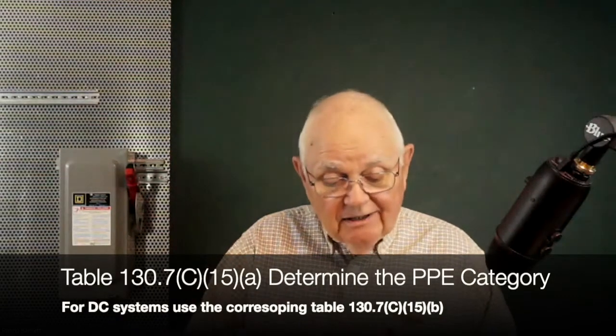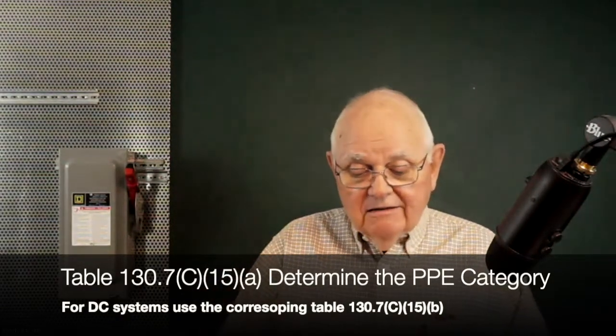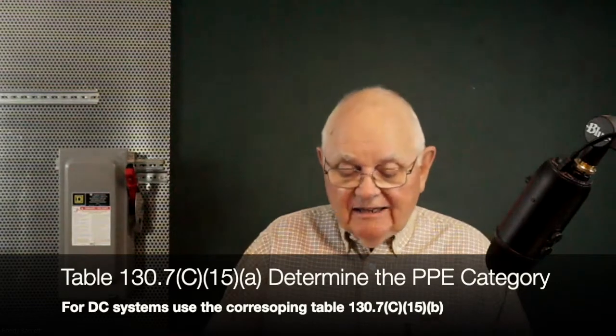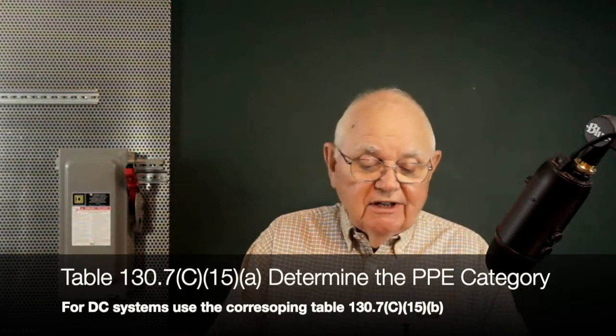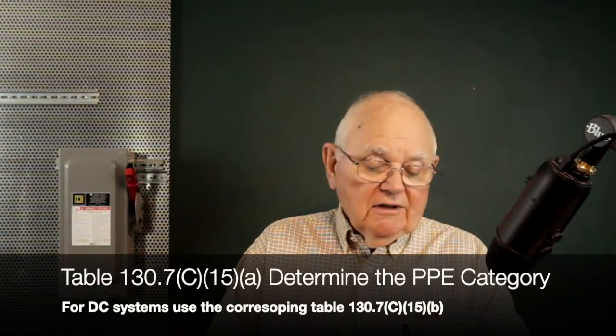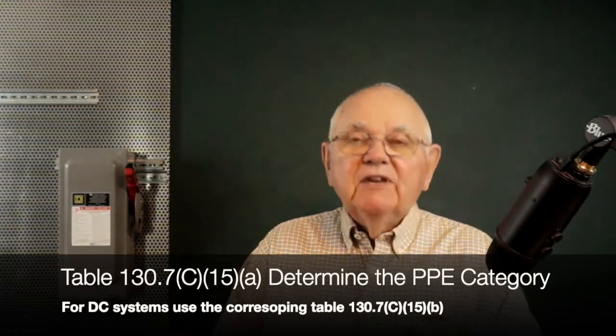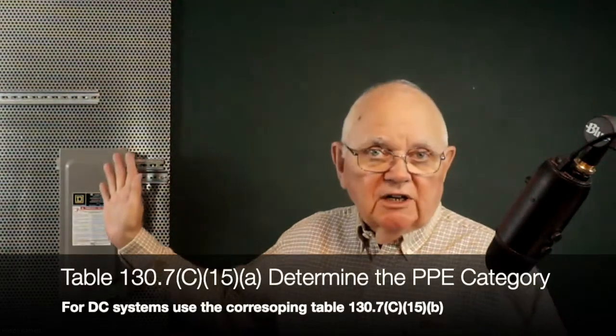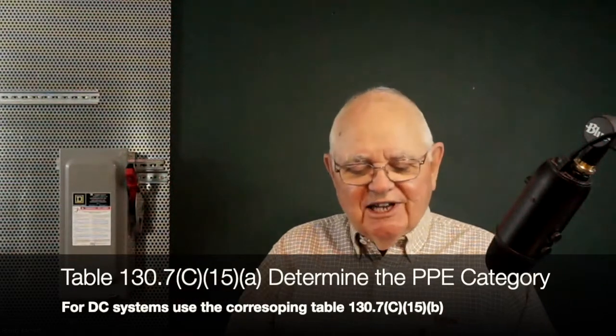So the next thing I need to know then is, what PPE do I have to wear? What's the category level? How many calories per square centimeter? So that's going to take me to the next table, which is Table 130.7(C)(15)(a), arc flash PPE categories for alternating current systems, or a corresponding Table 130.7(C)(15)(b) for DC systems. We're talking about AC, so we're going to use the AC table then.